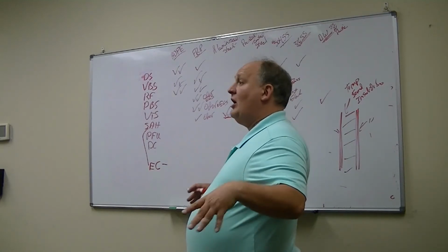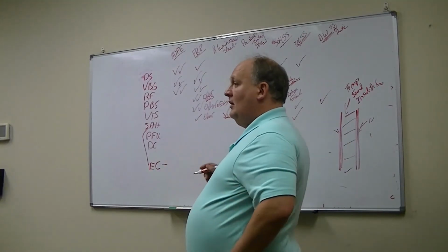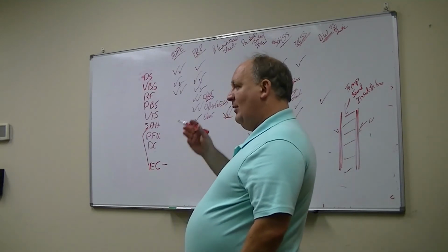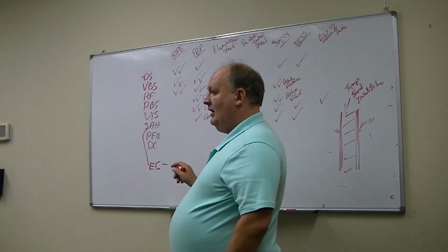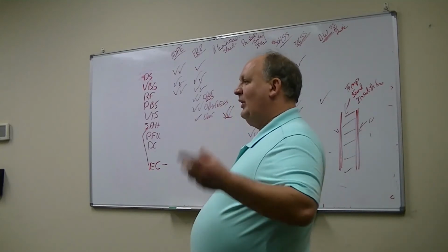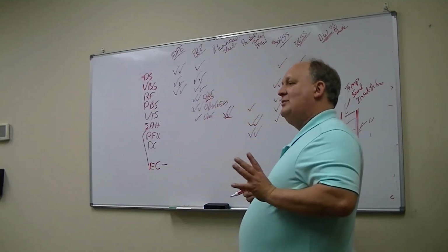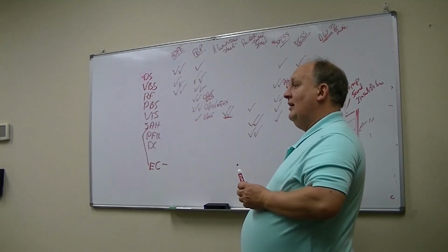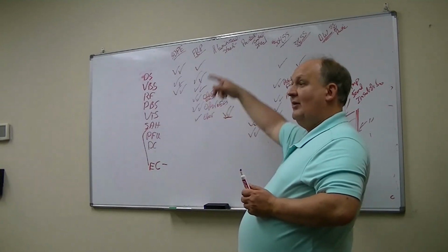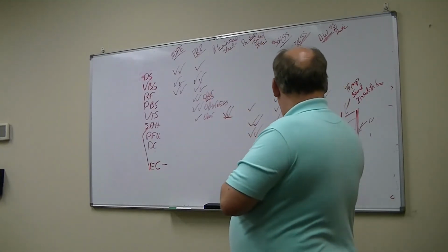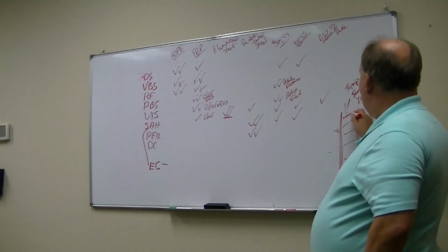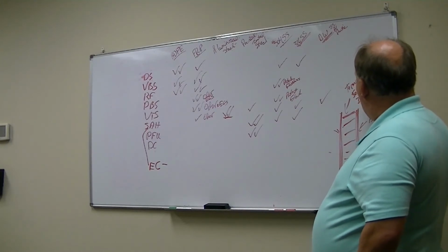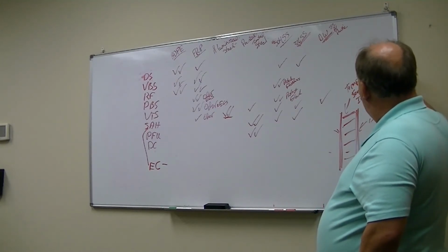But because that air coming off the grill is hot, there's always the possibility that you could have a duct fire coming off of the kitchen hood, because in a kitchen environment, you're always pulling greases and things up into the air, and a lot of times the duct coming away from that kitchen hood gets grease in it, and then they have a kitchen fire, and the fire actually goes up, captures through the duct. So a lot of times they'll require that we use double wall insulation for temperature and also really for fire protection, right?